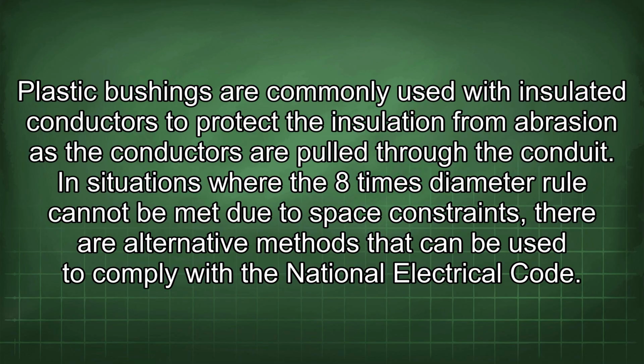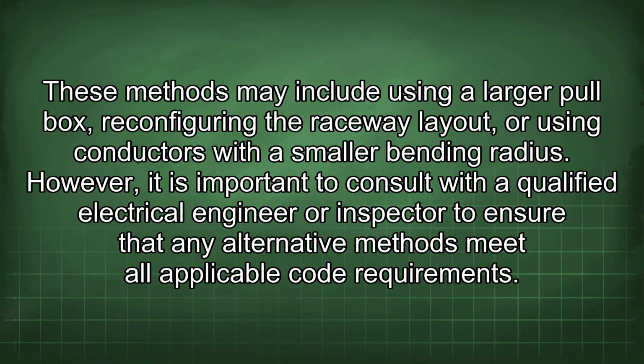In situations where the 8 times diameter rule cannot be met due to space constraints, there are alternative methods that can be used to comply with the National Electrical Code. These methods may include using a larger pull box, reconfiguring the raceway layout, or using conductors with a smaller bending radius. However, it is important to consult with a qualified electrical engineer or inspector to ensure that any alternative methods meet all applicable code requirements.